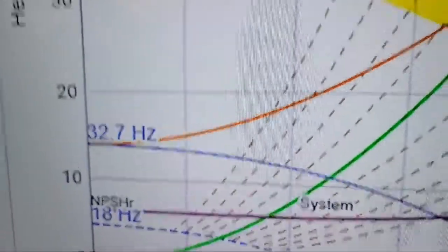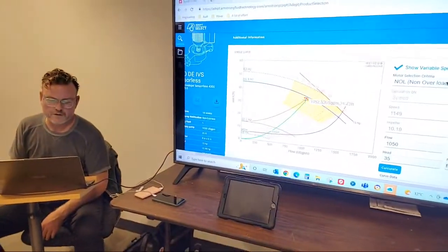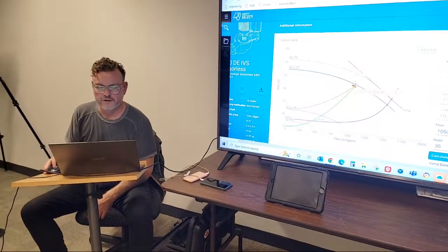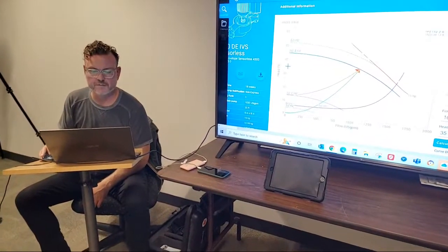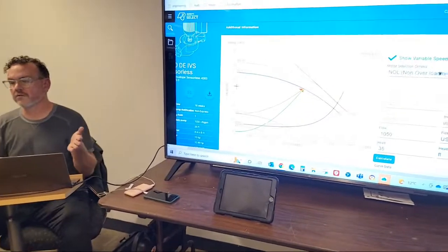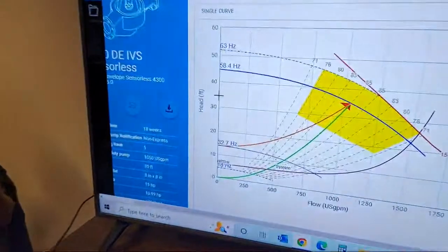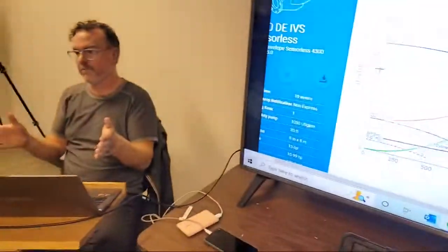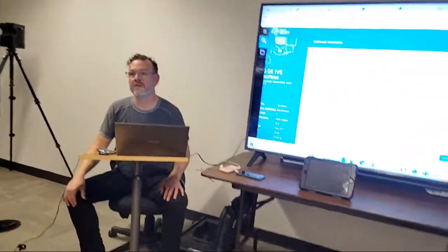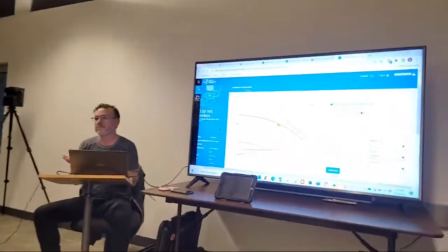So if we go up here, let's say, that's properly set up with the balancer and the controls contractor. But if you just put the sensor in the mechanical room, now you're almost at the design head because you're close to the pump. You're measuring the highest pressure point, which is closest to across the pump, yeah. So you can't meet the full flow and meet the minimum flow. It doesn't know because the sensor is too close to the pump, right?